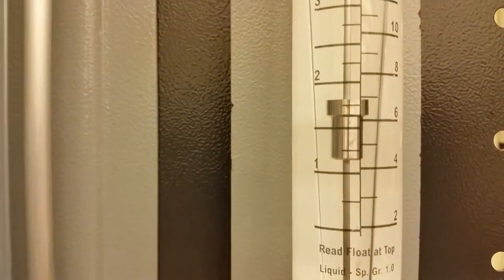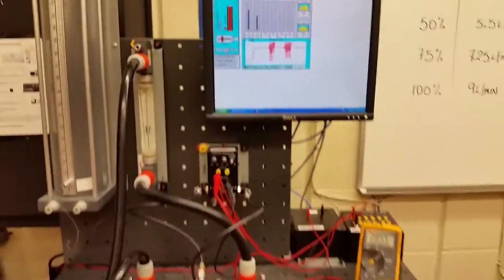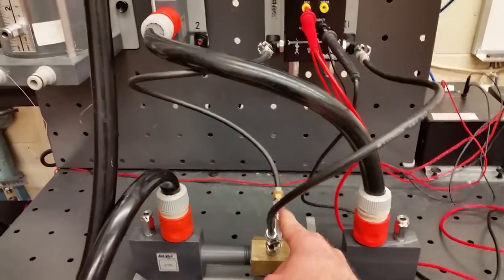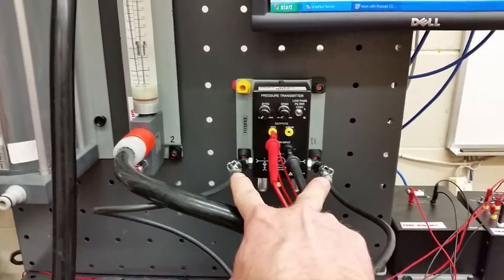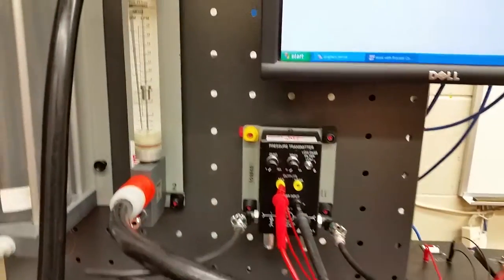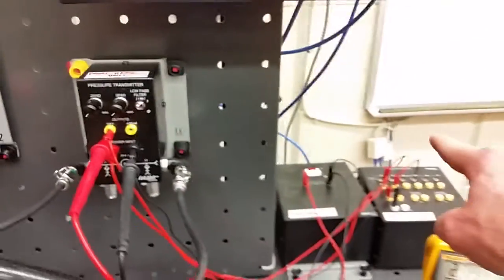You've been able to create closed loop control using the venturi tube. The venturi tube creates high pressure on the inlet and low pressure on the outlet. The DP cell uses a strain gauge or piezoelectric component to create a voltage — in this case a zero-to-five signal, but it could be a four-to-twenty — going back to the controller.